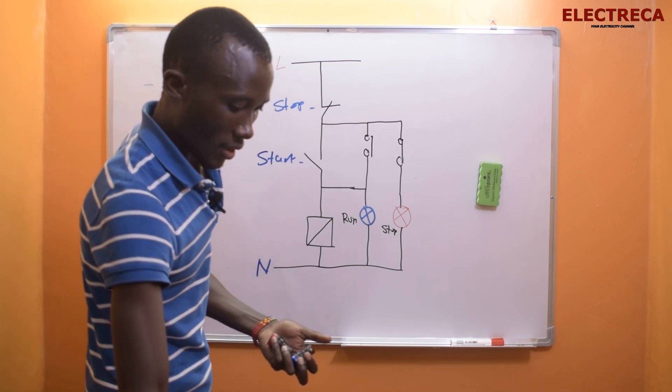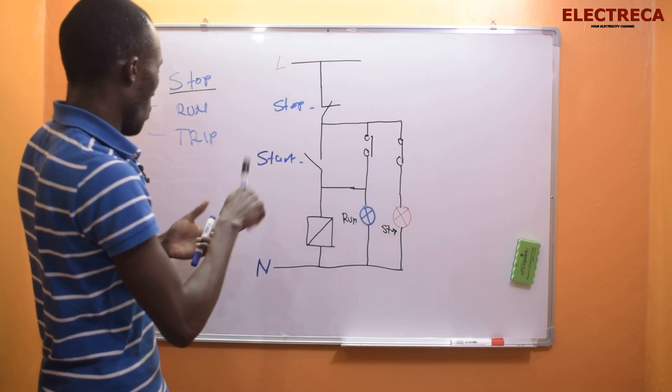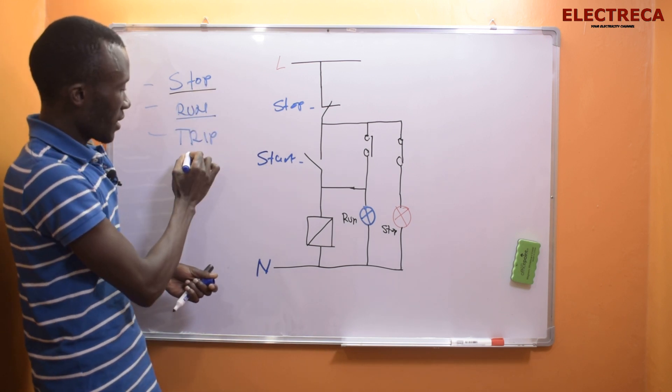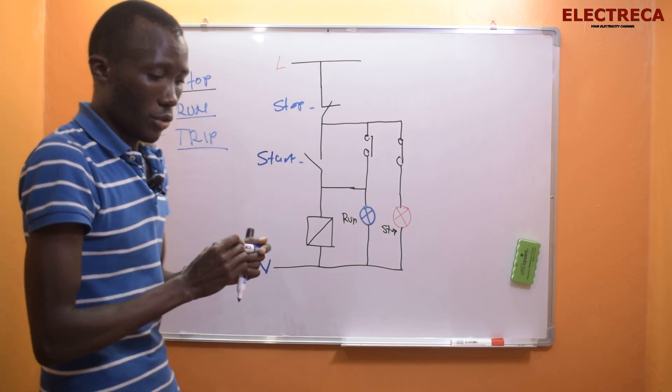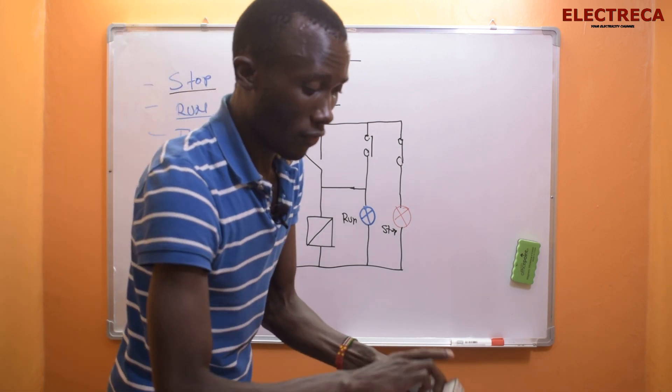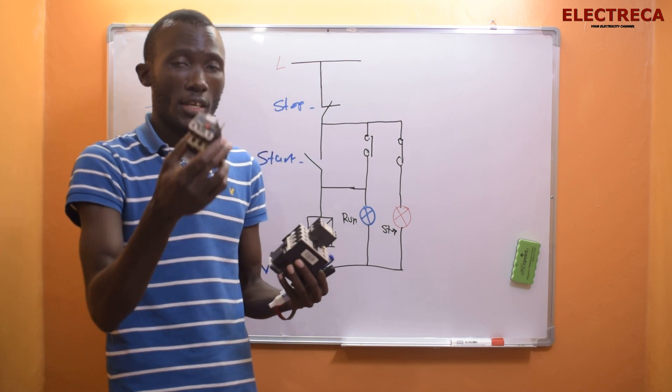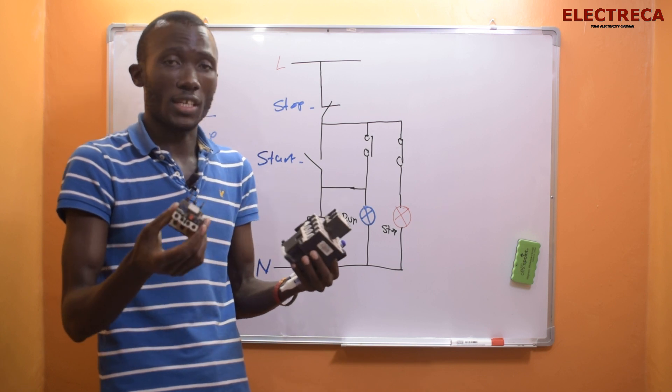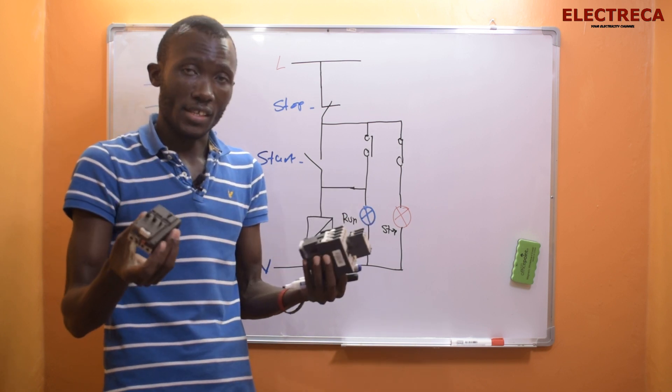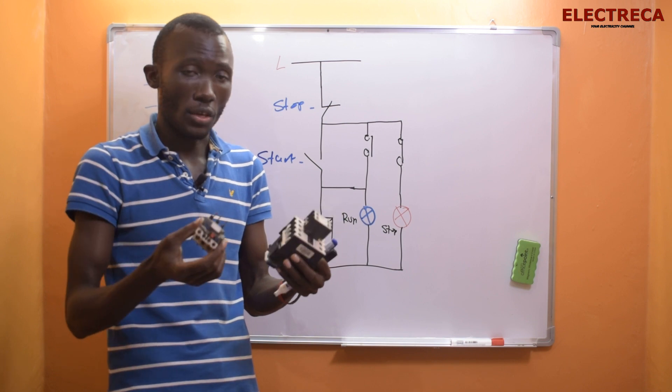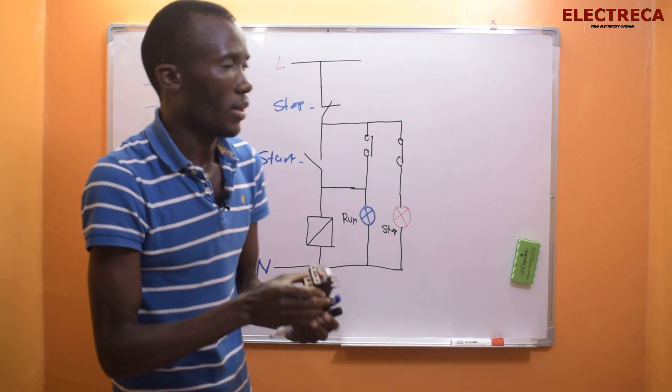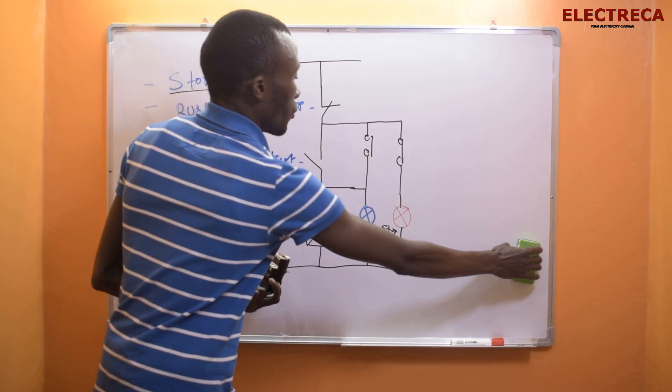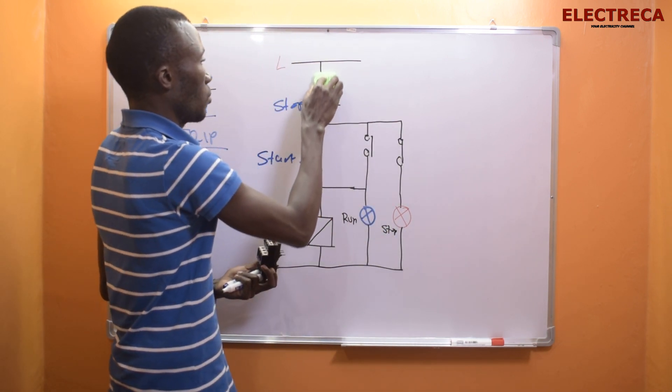We've already done stop and run, now let us tackle trip. Now trip, we have to involve this guy here - the overload relay. This overload relay clips on the contactor and it protects the contactor from overload current. This is how we connect an overload: first of all in your circuit here you have to indicate it, so we break here.